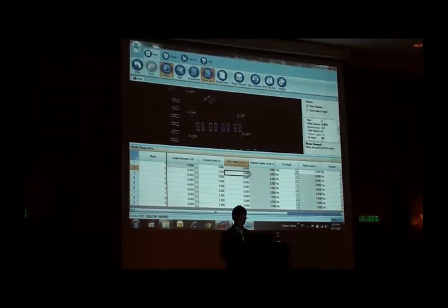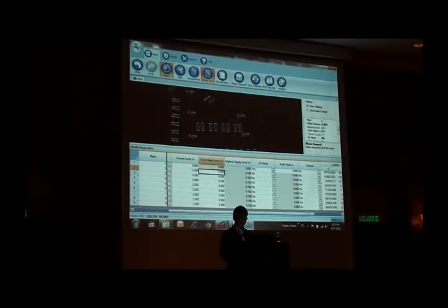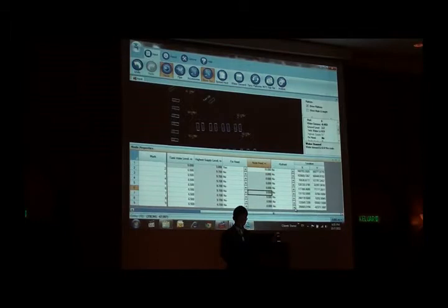and then the tank water level, I say 6.5. That means the building height plus the water tank depth. Okay, I just assume all the same. Okay, so we get the highest supply level. Also for the node head, for the fixed head, let's say it's 15 meter. So that's all for the hydrant.